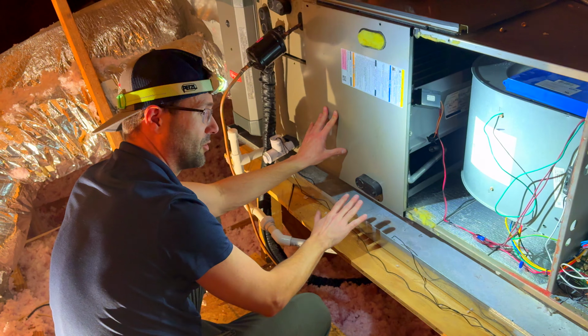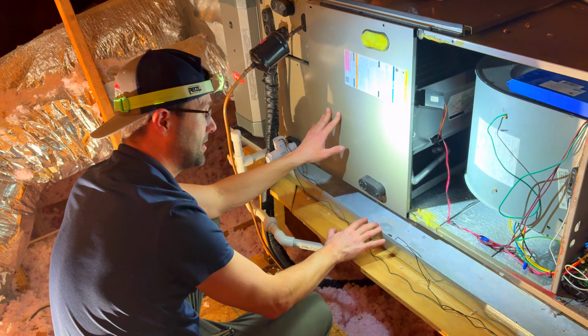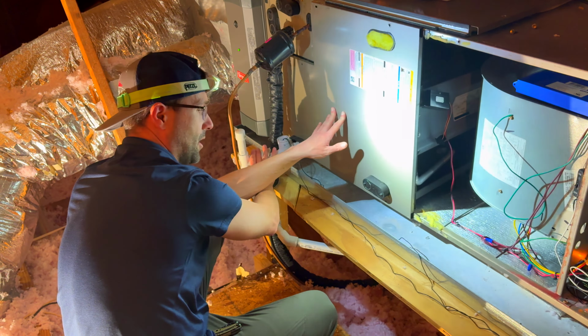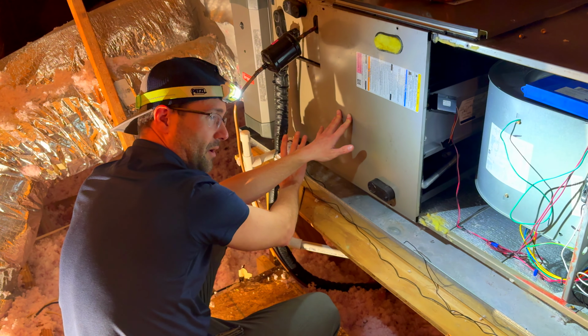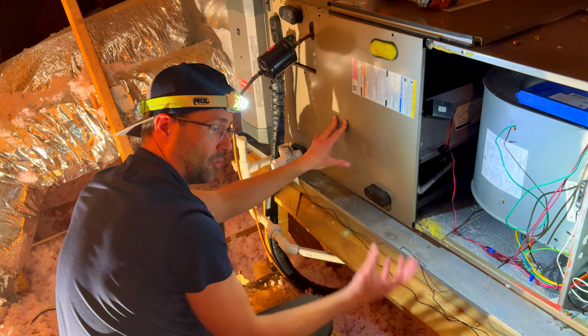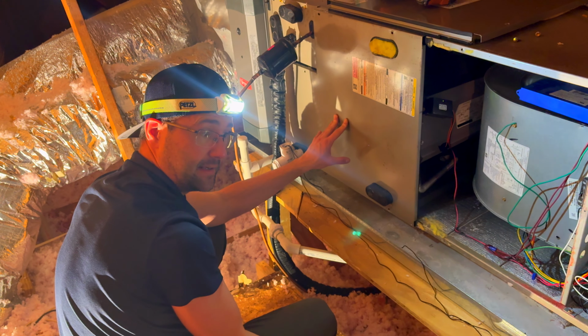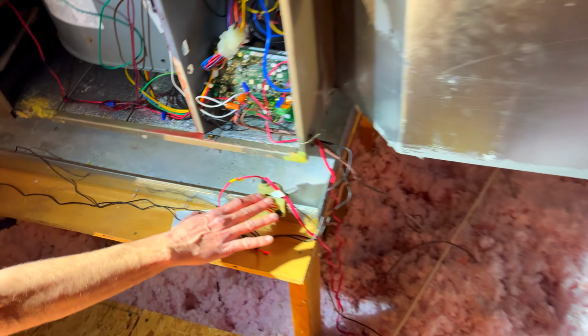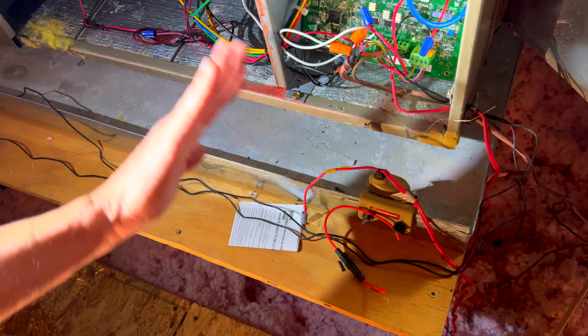Down below the unit, you've got your emergency drain pan. This is here just in case this were to ever clog up and any of the safeties were to fail, this would catch the water before it damaged the room or the ceiling or anything down below. And of course, we've got an emergency float switch here. This ensures that if this fills up with water, it will shut the entire system down.